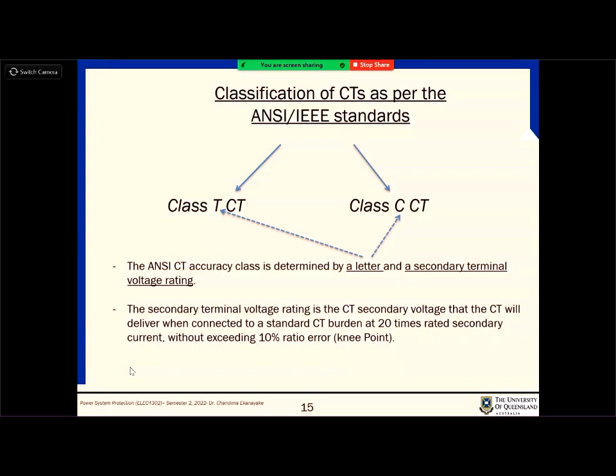I told you, when we select a CT, with the fault current, when you have the rated current, we multiply it by 20 to see whether the fault current is less than that or higher than that. The reason is this. The CT secondary voltage is what the CT will deliver when connected to a standard CT burden, right? We will come to what the standard CT burden is. What is burden? Burden is the load, the total impedance across the CT secondary. If you increase that resistance, it's harder for the CT, so that's why we call it a burden. This is at 20 times rated secondary current without exceeding 10% ratio error. See? Now what does it mean?